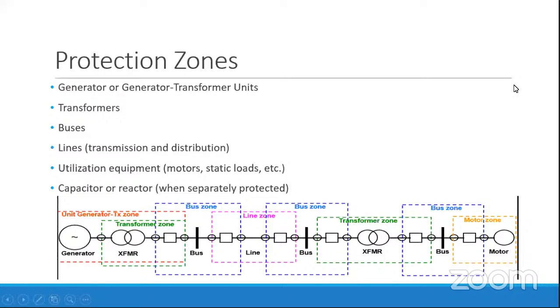Here in this figure you can see the generator, the transformer, the bus protection, which is the busbar, and the transmission line going to another substation or another bus, then another step-up transformer, then this bus, and the utilization equipment, which means a motor. Now the protection starts from downstream. It should protect the motor first, then the bus, and its upstream bus, in such a way that this protection provides backup to the motor zone. It provides protection to the motor. Then this bus should operate primarily, means this bus should isolate first when the fault occurs in this bus only.